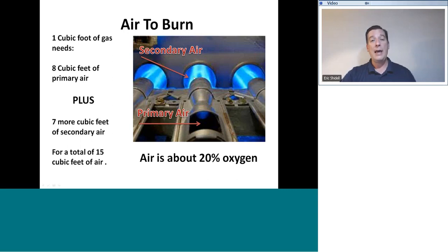Remember that air only has 20% oxygen. The remainder of air, the extra 80%, is primarily nitrogen. Nitrogen is an inert gas that doesn't mix with anything, it doesn't react with anything, and it doesn't burn. It doesn't sustain combustion. But it's there. When we have a cloud of fuel gas plus oxygen plus nitrogen, what is going on is that fuel gas is trying to combine with the oxygen. But there is so much nitrogen there that it is getting in the way. It is physically in the way, preventing oxygen and fuel gas from coming together.